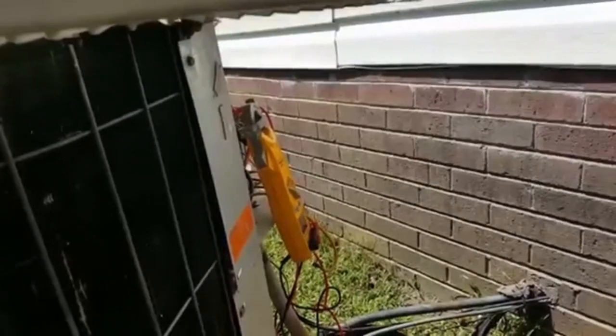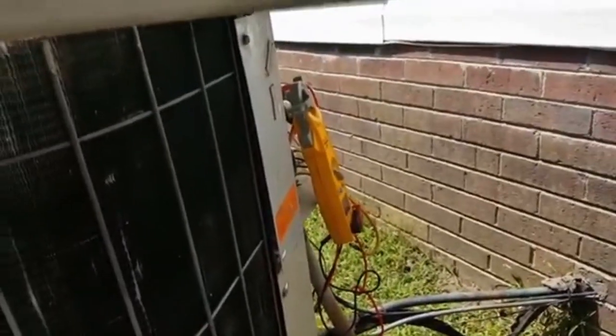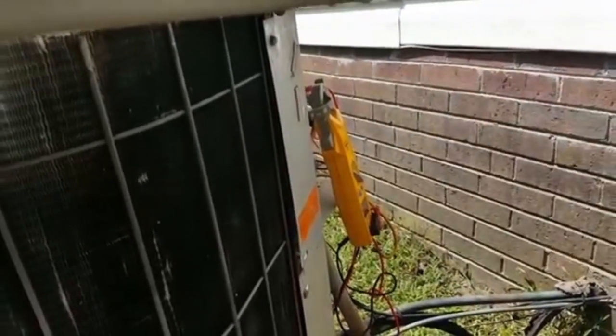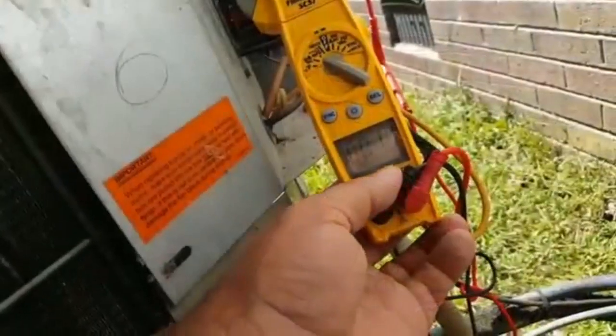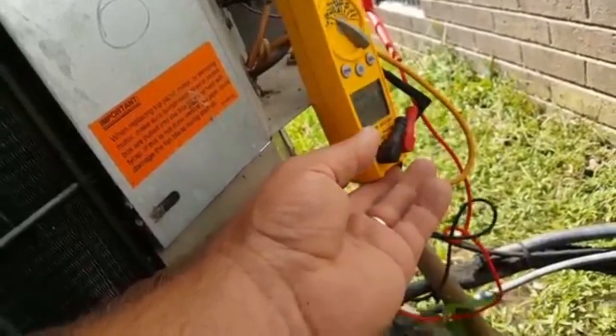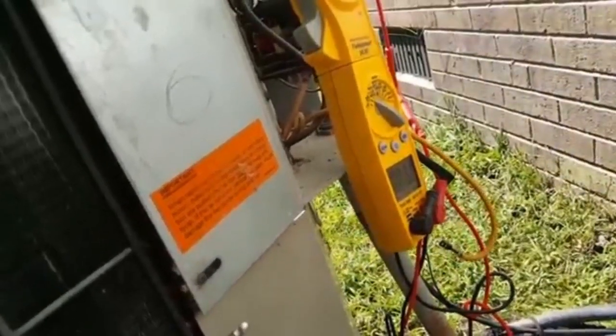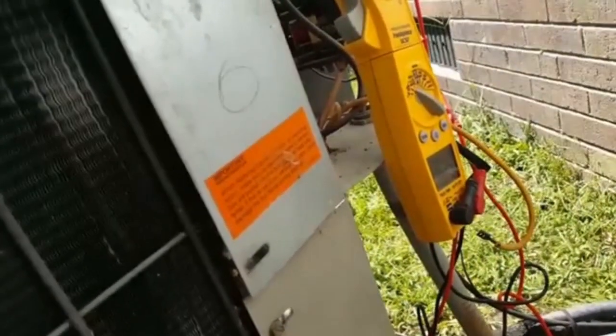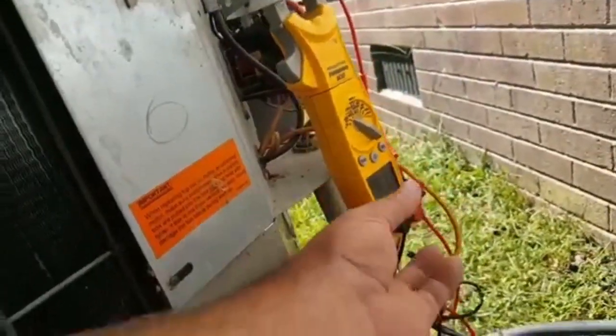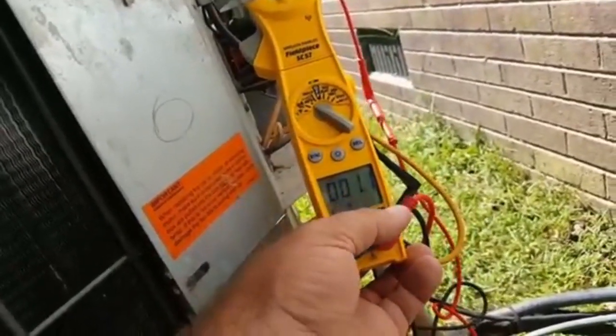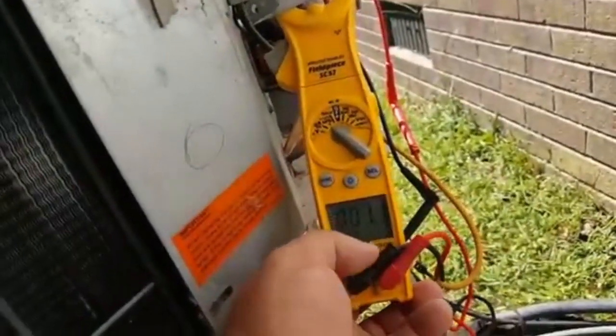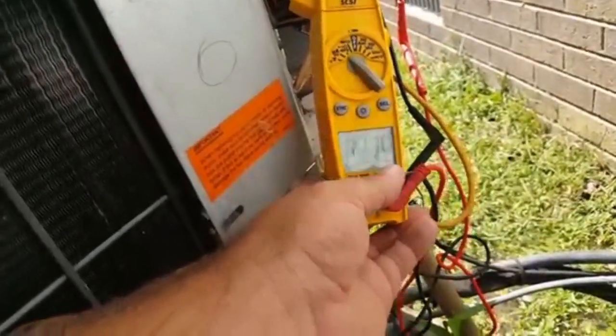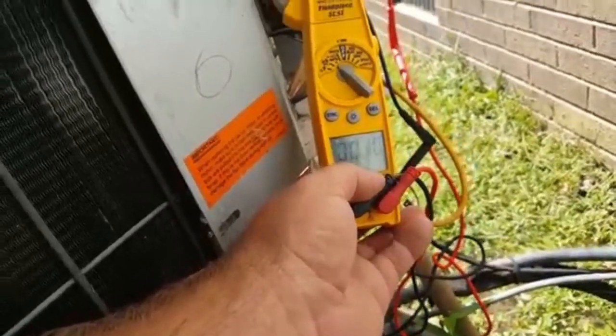Even though I haven't disconnected the leads to the compressor, I'm going right from the contactor. The fan's in thermal overload too, so whichever one comes back first tells me which is which—the fan will show a higher ohm reading. We've got 1.1 ohms now, which is the compressor itself, out of thermal overload. When you see a higher value in the double digits, that's the fan—around 14 or so—and if you spin the blade, you'll see the value change. But once the compressor's out of thermal, it stays at a low single-digit ohm reading.